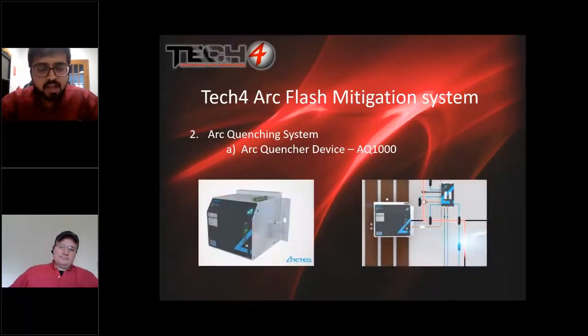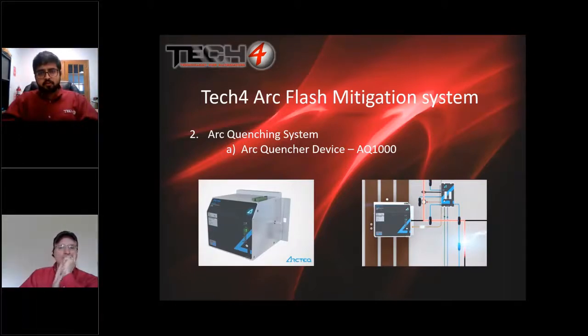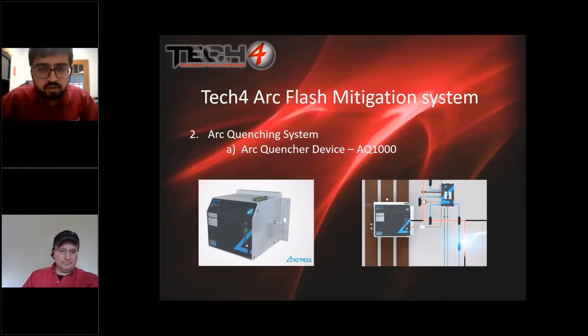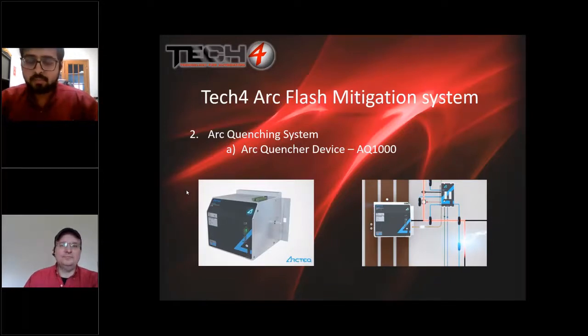So that's the AQ1000 low voltage arc quencher device. So the arc quencher, when it receives a trip signal from the AQ110, creates a low impedance path. It shorts all the 3 phases, due to which there's a collapsing of the voltage, which extinguishes the arc, and the upstream breaker can trip for the short circuit. So that's the AQ1000 device, and like Bucky said, it's resettable. It's the only resettable arc quencher device in the market.